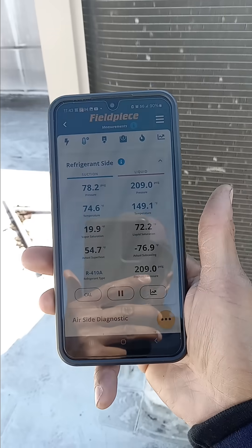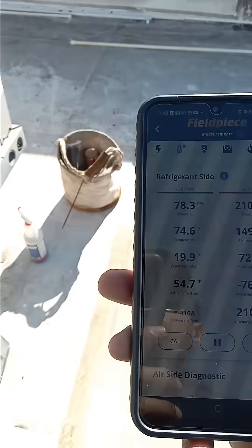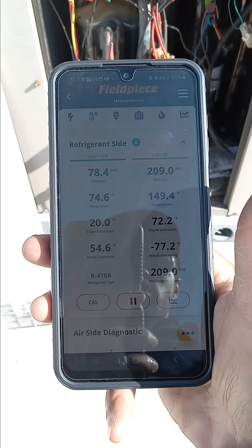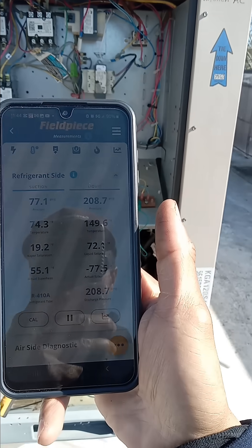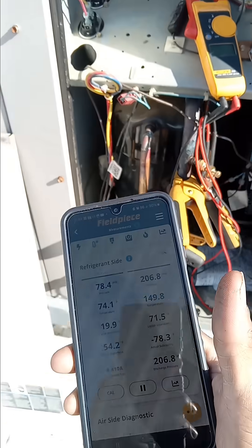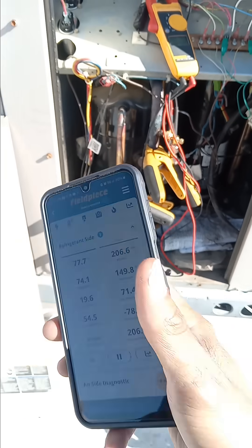I put my gauges on, and as you can see, circuit number two is low on charge. The superheat is 55 and my subcooling is sitting at about minus 77.